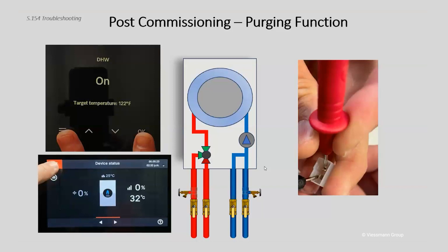Post commissioning — if I just finished a retrofit, maybe added some baseboard or replaced a system pump and had to drain the system down a bit, now I want to get the pressure back up. I don't have to go back into commissioning. I can activate these functions using what we call actuator tests with both boilers. With the 100, make the 'V' with your fingers across the OK and menu keys. With the 200, push the menu key and get into service.